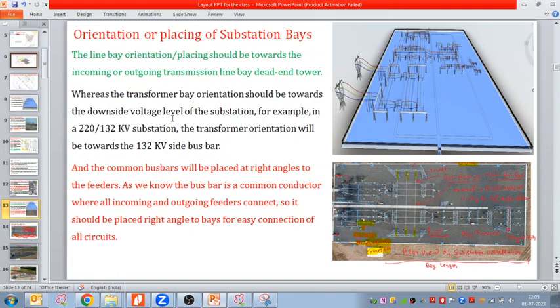Coming to the next statement: the transformer bay orientation should be towards the downside voltage level of the substation. For example, in a 220 by 132 kV substation, the transformer orientation will be towards the 132 kV side bus bar. Because we are stepping down with the help of the transformer to another voltage level, and after stepping down, that voltage needs to be fed to a common bus bar, and from that common bus bar we will take the other low voltage line bay.